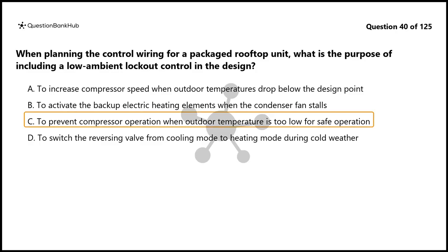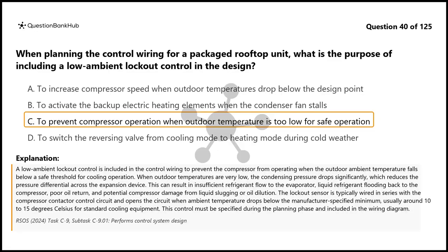The correct answer is C. A low ambient lockout control is included in the control wiring to prevent the compressor from operating when the outdoor ambient temperature falls below a safe threshold for cooling operation.